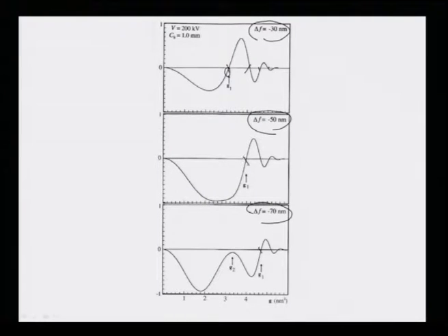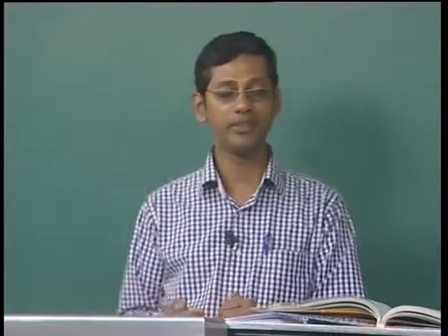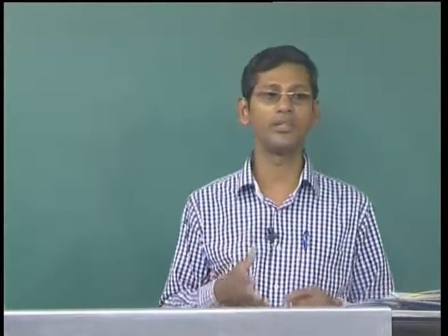This is the first crossover at the 0 g axis. So, all the electron beams will have nearly constant phase out to this point, and this is what is required to obtain the best possible resolution or information in electron microscopes. The best performance will be expected from a microscope up to the first crossover value on the g axis, unless we do a lot of image processing later on, that is, improve the contrast by some other means.